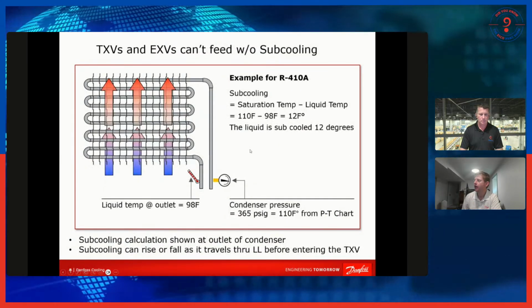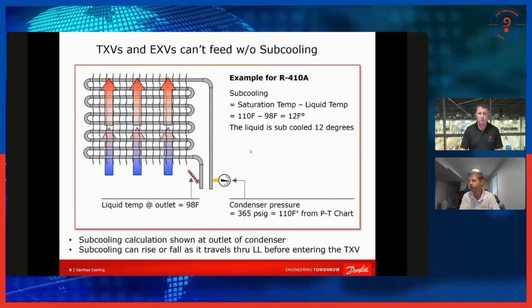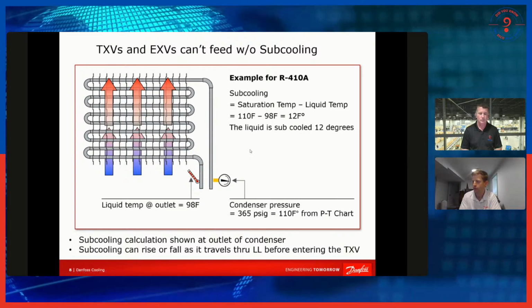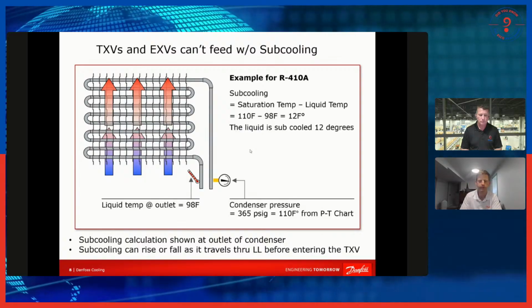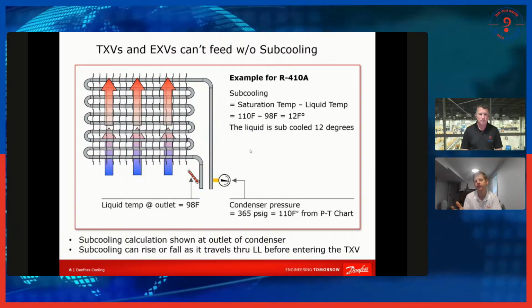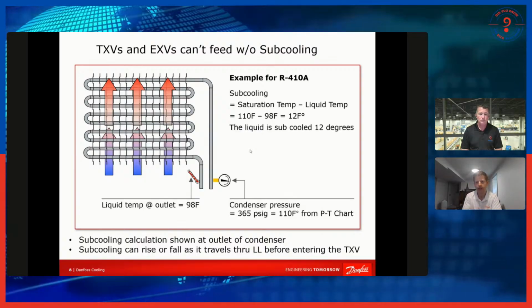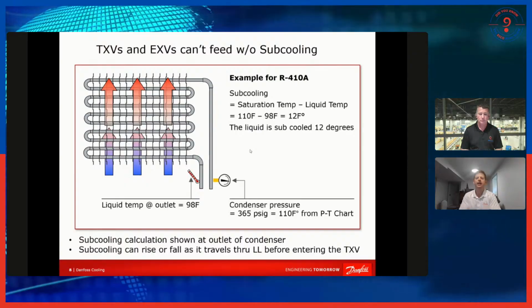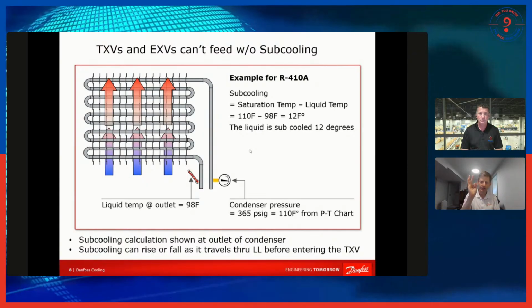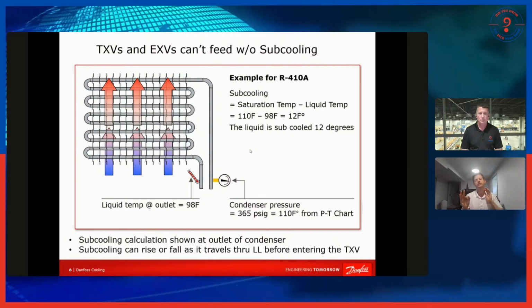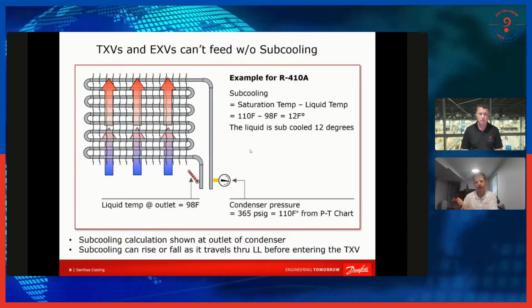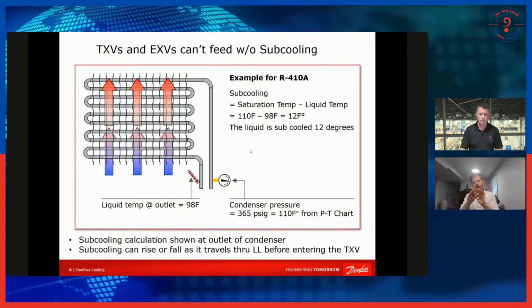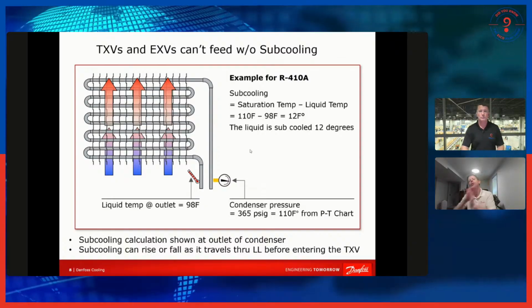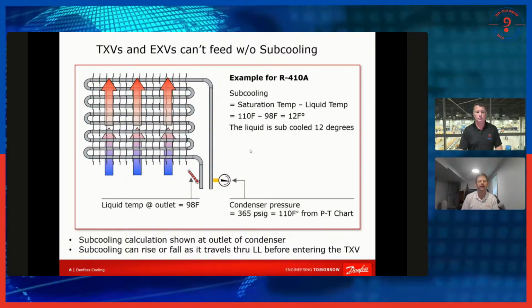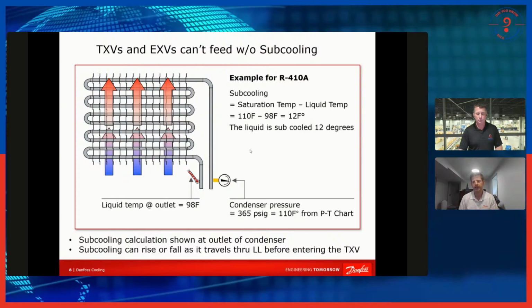Superheat's important. So is subcooling. And I'm sure everyone's seen charts like this before where you go through and calculate subcooling, but an EXV needs subcooling to feed, the same way that a TXV does. It's a very small opening in any TXV or EXV, and it's meant to have 100% liquid on it so that it can feed. If vapor starts getting in the way, because it's such a small opening, it won't be able to get enough through, and you'll underfeed as a result.